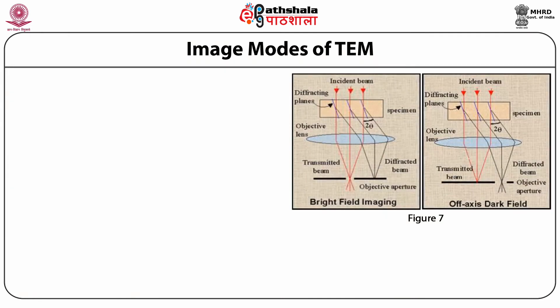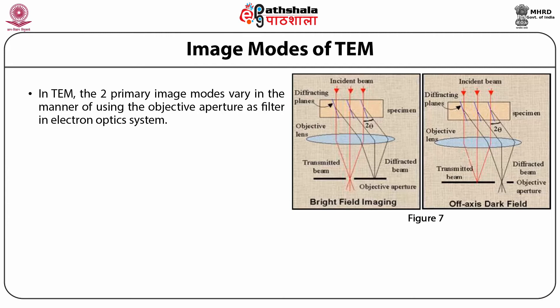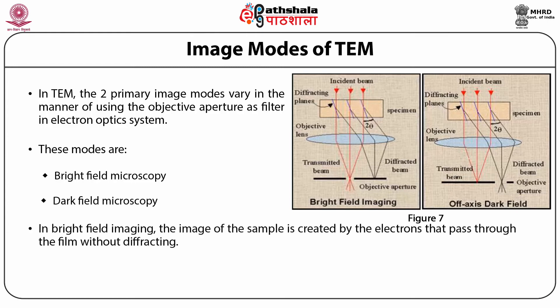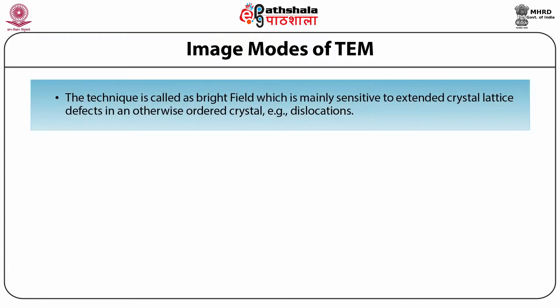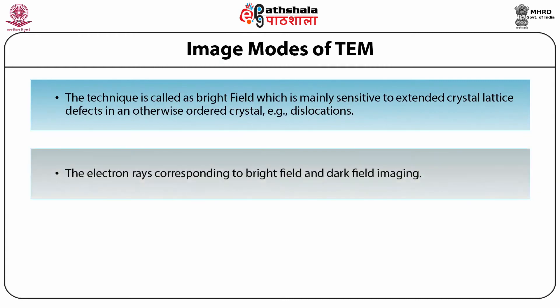In TEM, the two primary image modes vary in the manner of using the objective aperture as a filter in the electron optics system. These modes are bright-field microscopy and dark-field microscopy. In bright-field imaging, the image of the sample is created by electrons that pass through without diffraction; a diaphragm is used to stop the diffracted electrons. In dark-field imaging, the image is formed by the diffracted beam, as shown in figure 7. Bright-field imaging is mainly sensitive to extended crystal lattice defects in an otherwise ordered crystal, for example, dislocations.